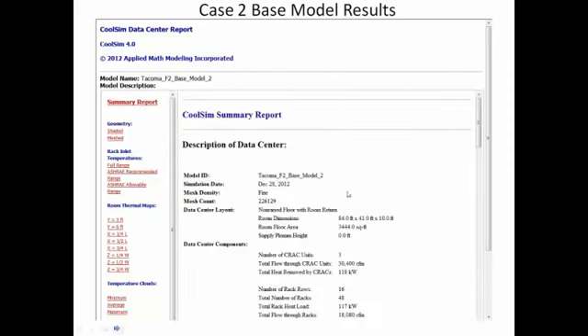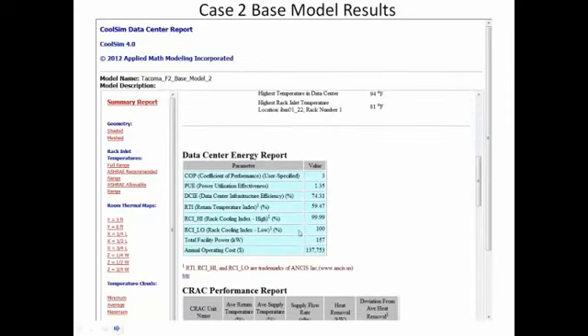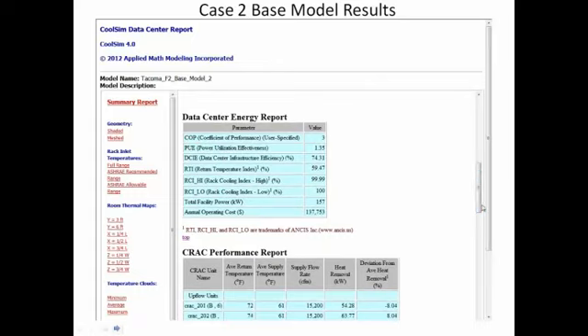So let's take a look at our summary report again, and we'll go right down to this data energy report section. And you see here the RTI in this room is 59%. Now, the RCI high is 100%, so everybody's happy in terms of cooling. Nobody's too hot. RCI low is 100%, which means we're not too cold. So at first blush, you would say these are pretty good statistics, that we've got both high and low at near 100%. Tell me what's wrong. Well, what's wrong is the RTI is 59%. So the amount of energy being dumped into that room is extremely high compared to what it needs to be.